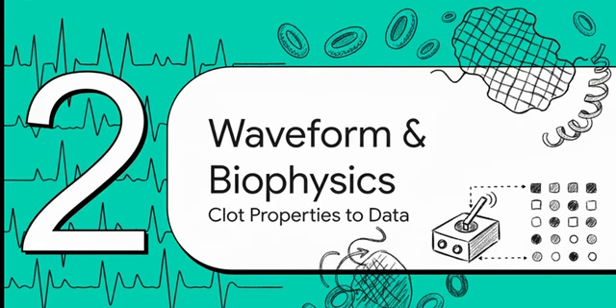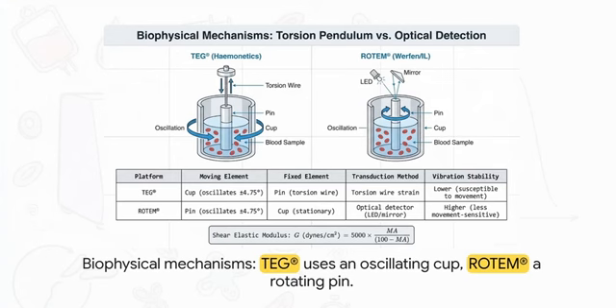Understanding the waveform anatomy and its underlying biophysics is key to seeing how these systems transduce mechanical clot properties into clinically actionable data. Both TEG and ROTEM operate on an identical biophysical principle. They detect the mechanical coupling that occurs between a cup and an immersed pin as a whole blood clot forms. The mechanical distinction is straightforward. In TEG, the cup oscillates. In ROTEM, the pin oscillates. The clinical relevance of this seemingly minor distinction, however, lies in the transduction method. ROTEM's optical detection system confers superior stability against external vibration, a non-trivial consideration in a busy operating theater, or, for that matter, during patient transport.